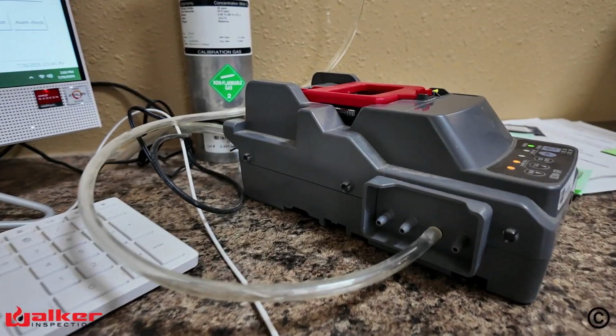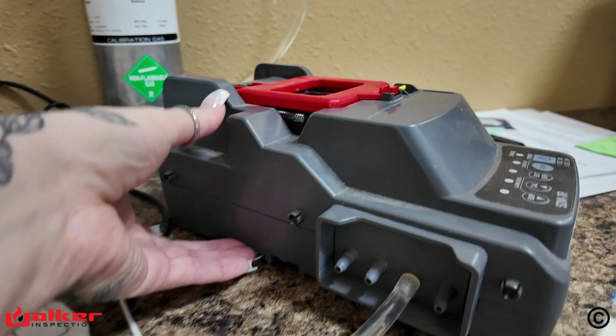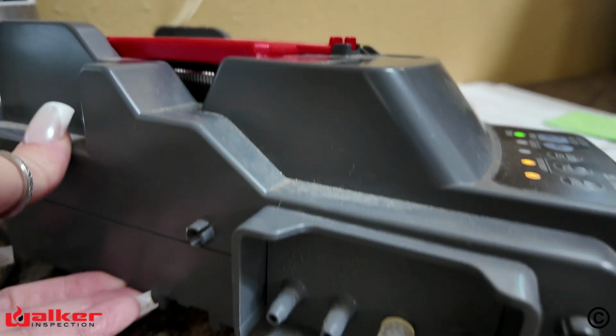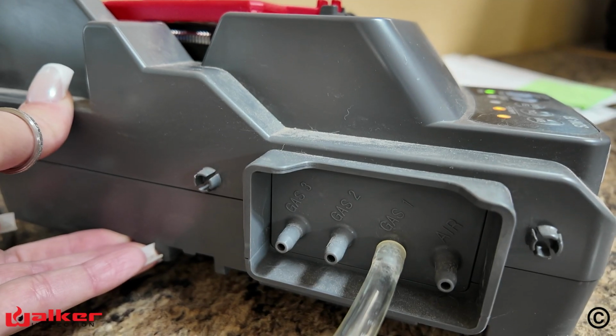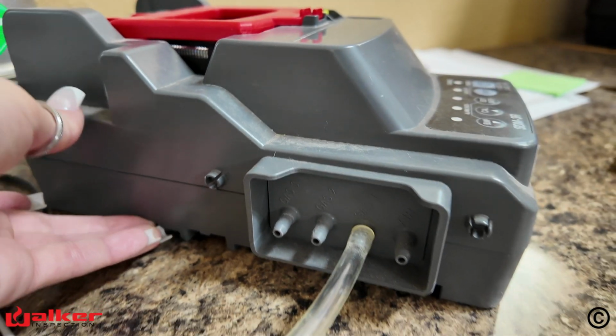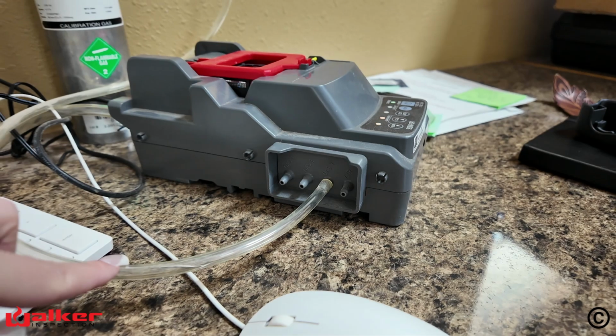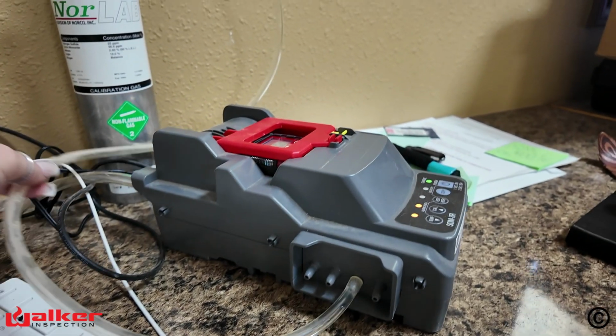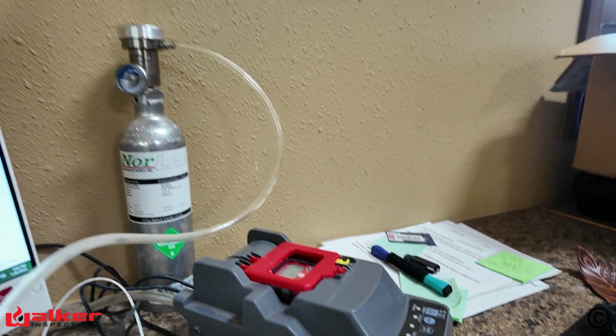the monitors. Then, you will need to ensure that the gas bottle hose is hooked up to the right nozzle on the calibration station, which will be gas 1. This hose has to be connected to gas 1 only. It cannot be hooked to any of the other nozzles as it will not calibrate or bump test correctly and will cause the monitor to fail.